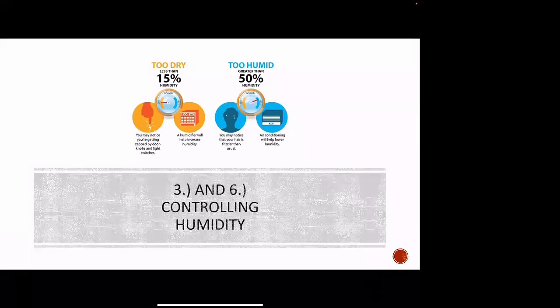Understand dew point, have the conversation with the homeowner, make sure they're aware of it. Any control that we put in should have an outdoor sensor with window protection set up on the controller. And during the summer, I really don't want it any higher than 50% humidity in the home or in areas of the home, such as a basement or crawl space.